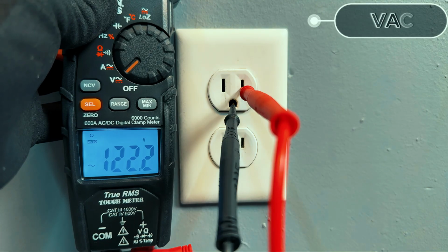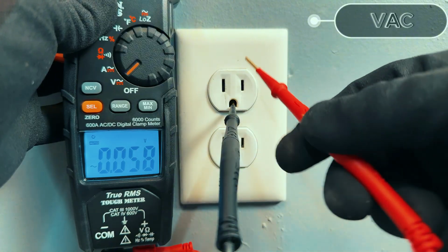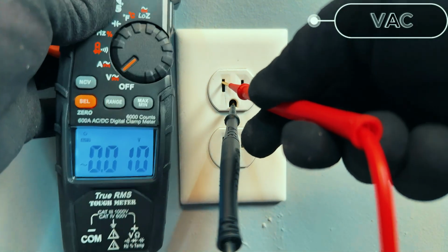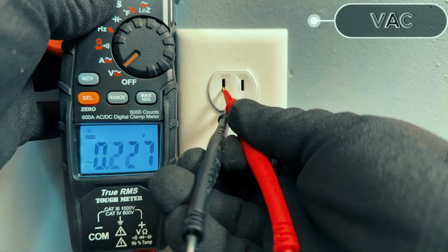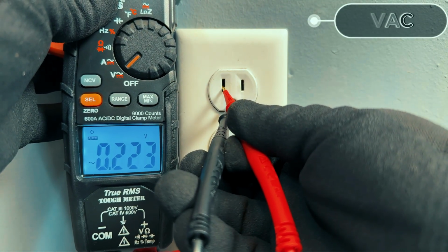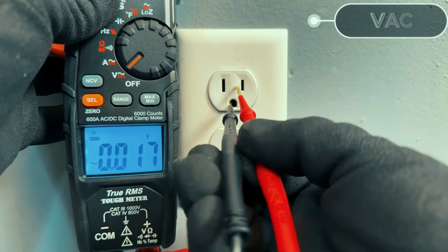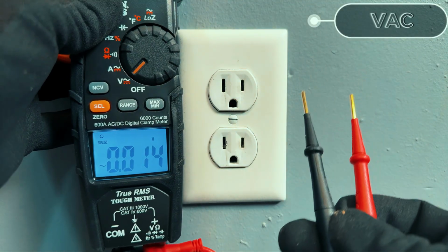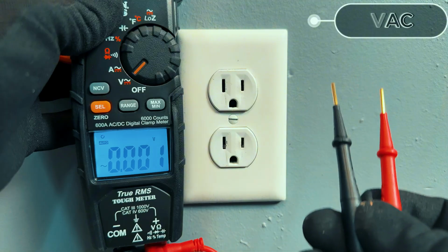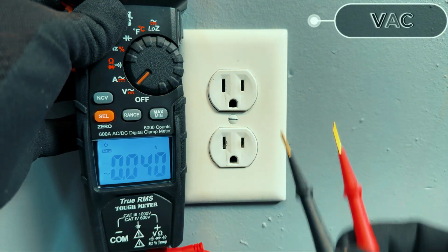Finally, test neutral to ground. This should read very close to 0. If not, there could be a grounding issue. All we're going to do is go right here to our neutral. We're not getting anything, so that's proper polarity. Now, if I was getting voltage here, if I was getting 120 here and nothing from line to ground, that could mean that I have reverse polarity, which could affect the appliance operation or cause unintentional failures. And that is how you check AC voltage and proper polarity of an outlet.